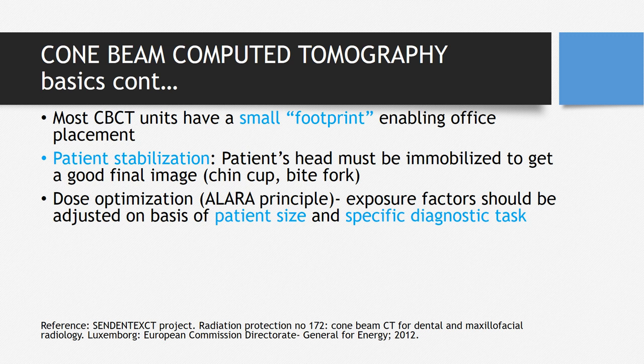Patient stabilization is very important — the patient's head must be immobilized to get a good final image. Chin cups or bite forks present in the machine allow you to stabilize the patient's head with ease. When it comes to dose optimization, the principle of ALARA applies — exposure factors should be adjusted based on the patient's size and specific diagnostic tasks. The CBCT software allows you to adjust all of these to give your patient the least exposure with the best image.